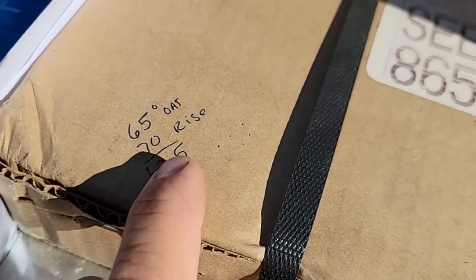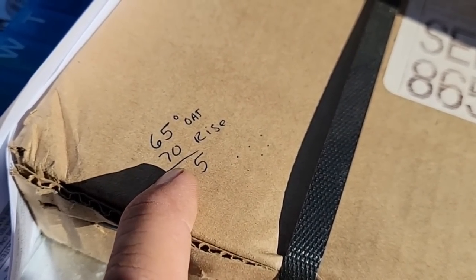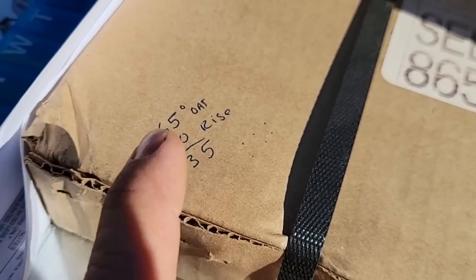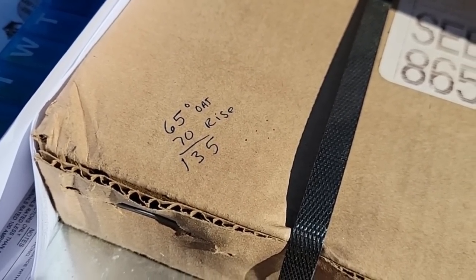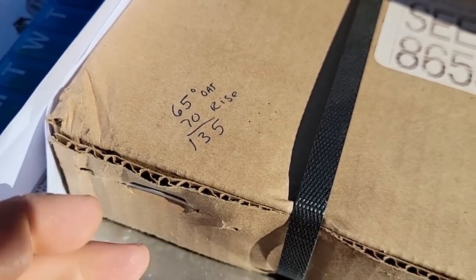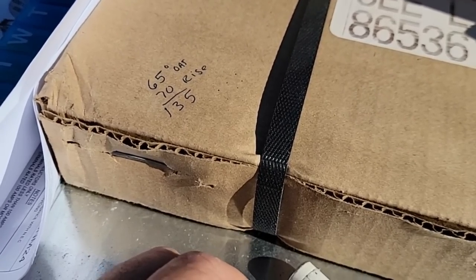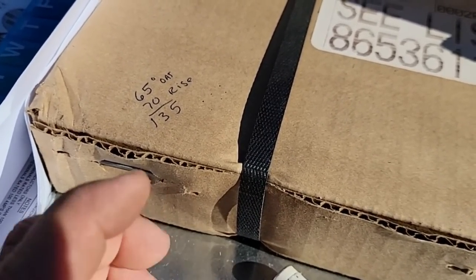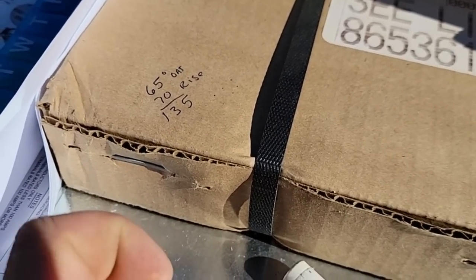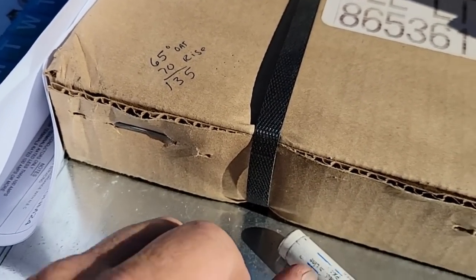Now, something to keep in mind here, say it's 65 out and we have a 70 degree rise built into this, the discharge is going to be 135 degree air. Well, yeah, because it's going to measure the discharge temperature. It's going to try to maintain 70 degrees. That's probably a lot of what we got going on here.